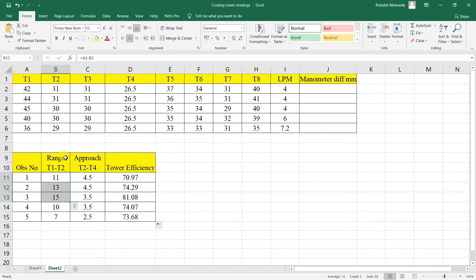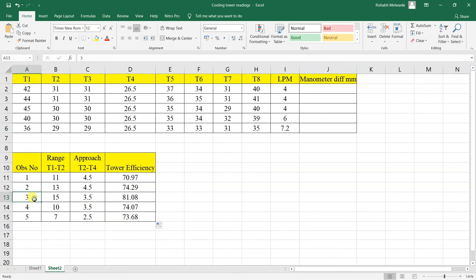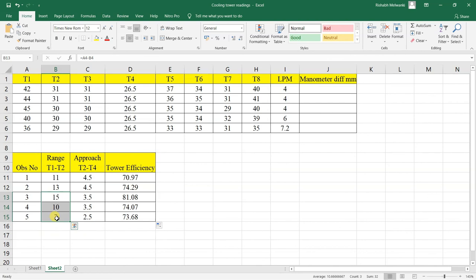For observations three, four, and five, the water flow rate is increasing while the air flow rate is kept constant. Therefore, range is decreasing because the time available for heat transfer between water and air is reduced. This concludes the cooling tower experiment.